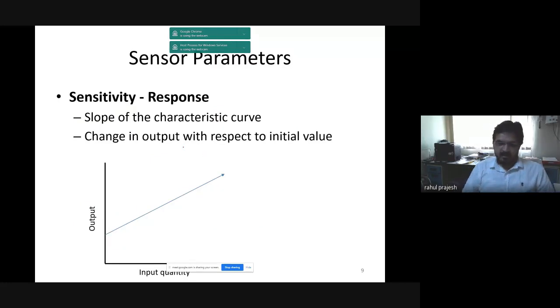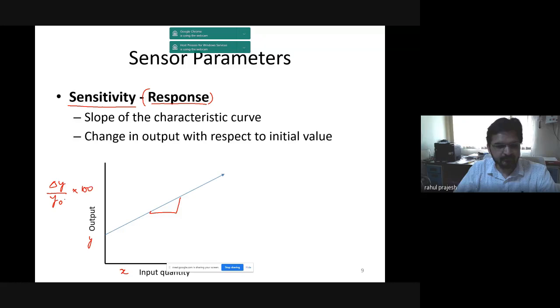Now, if you are talking about sensors, it is important to understand different parameters related to sensors. The first very important parameter is sensitivity, and sometimes we call it response also. Sensitivity is the slope of the characteristic curve. Characteristic curve means you have some input quantity on the x-axis and the output quantity on the y-axis. If this is a linear curve, the slope of this curve will give you sensitivity. But sometimes you take it as response. Response is basically the change in y-axis with respect to the initial value of y-axis. And sensitivity is the change in y-axis with respect to the change in x-axis.